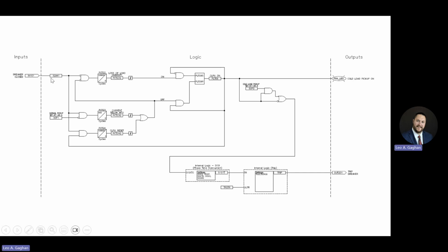So let's say the breaker opens. When the breaker opens, this becomes, oh, sorry, I had that wrong. Going back to breaker close. Breaker close, we have a 1. Because we have a 1, we have a 0, nothing happens here. We come down here, we have a 1, and our current is below our minimum pickup, so we have a 0. This becomes a 1. If that happens for 900 cycles, this will have a rising edge trigger.